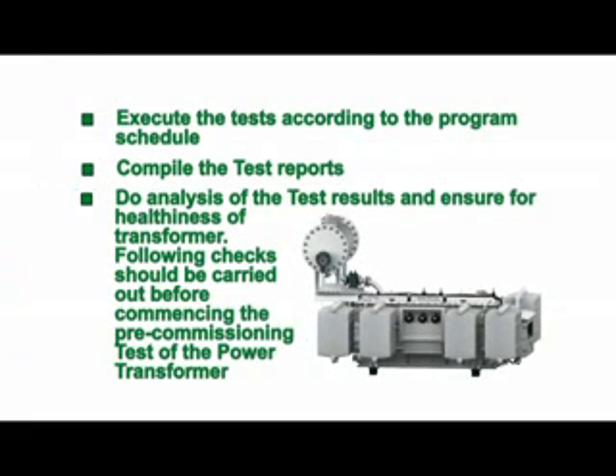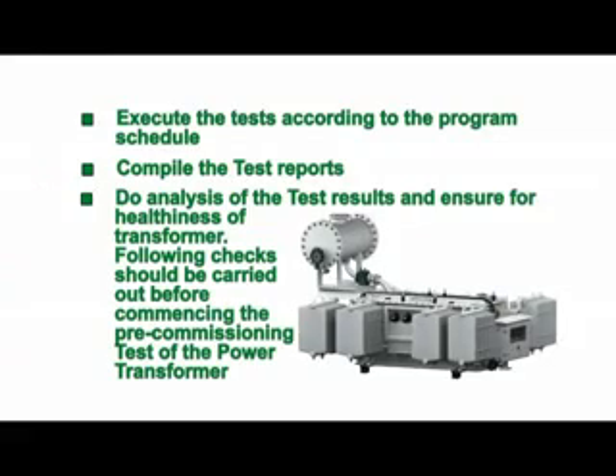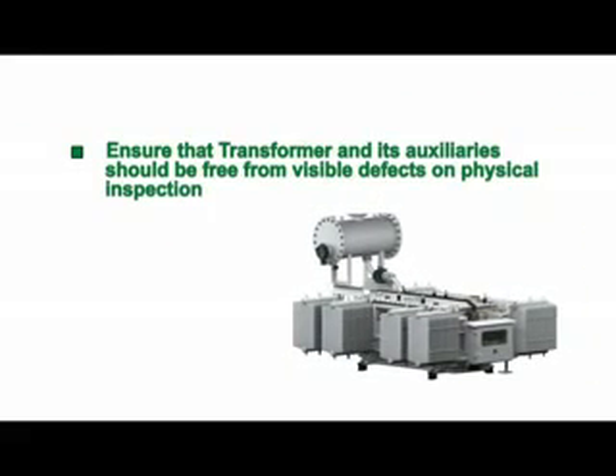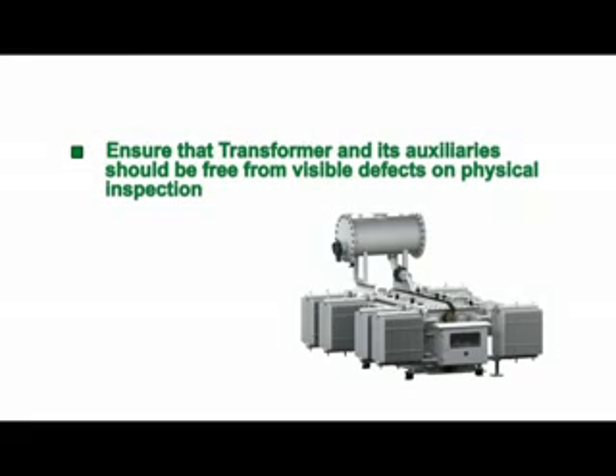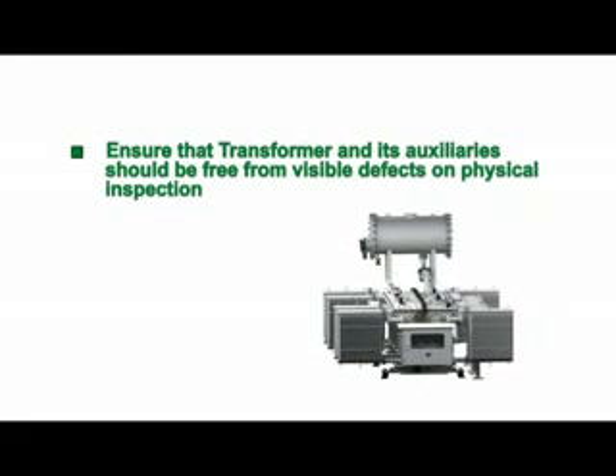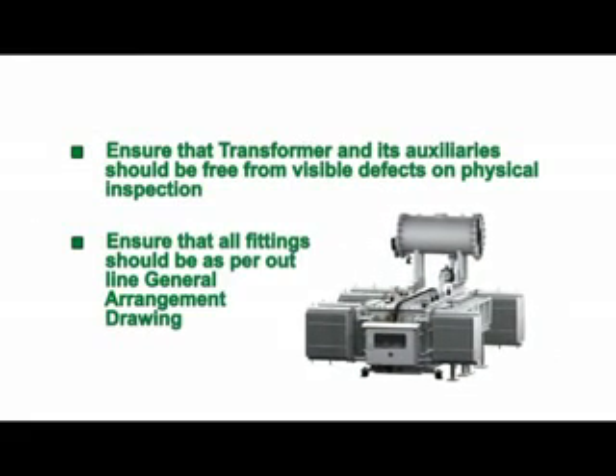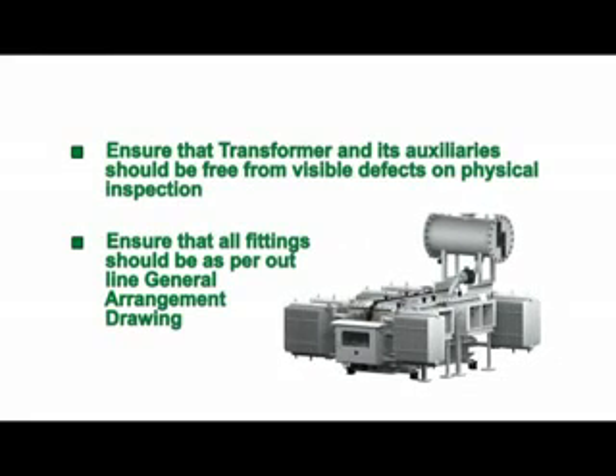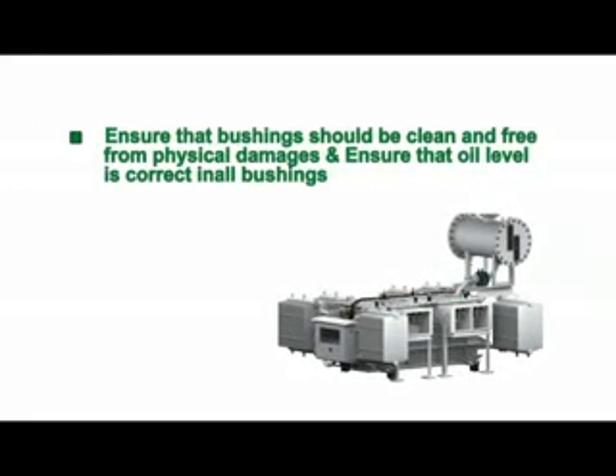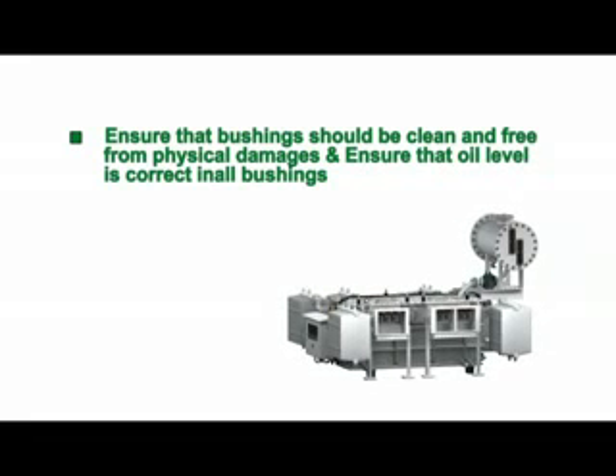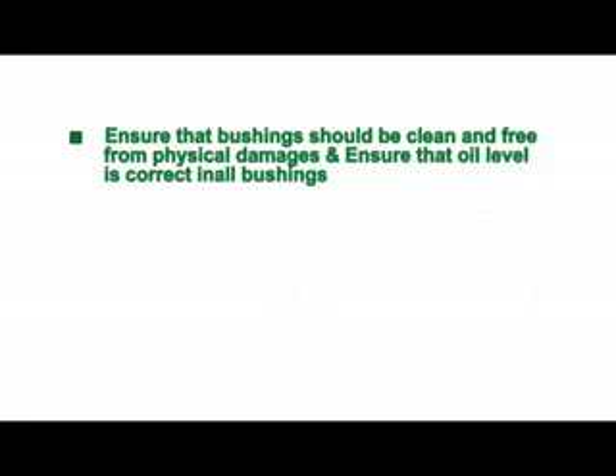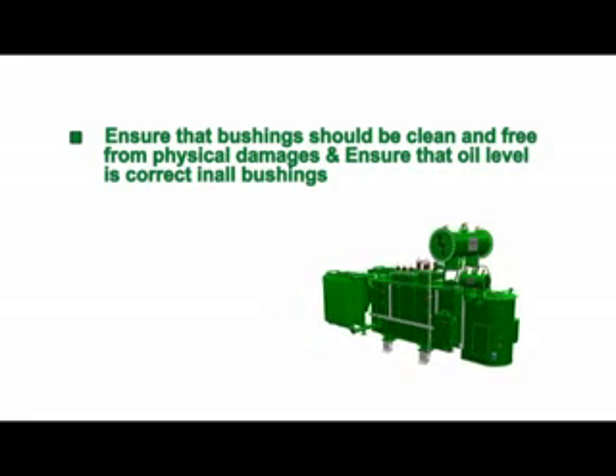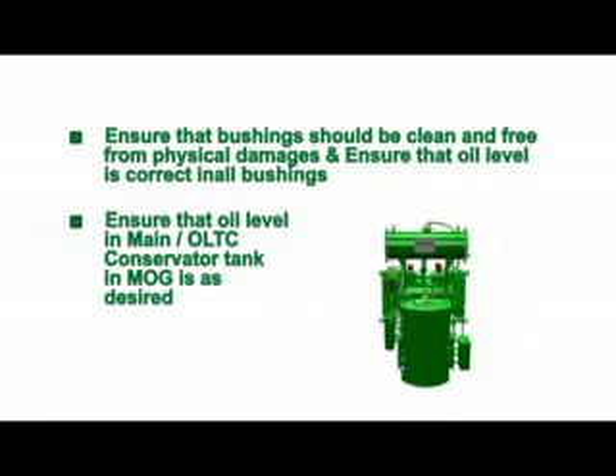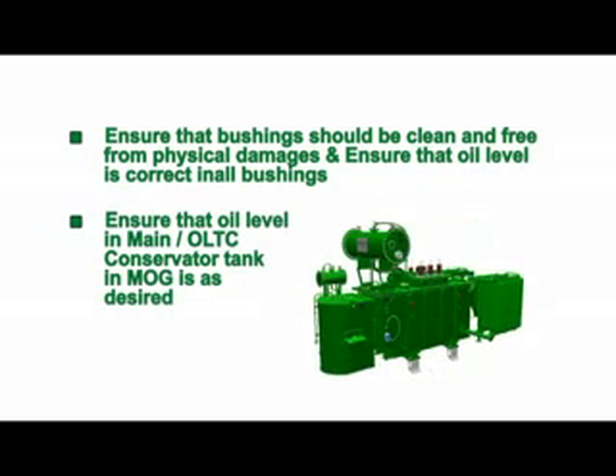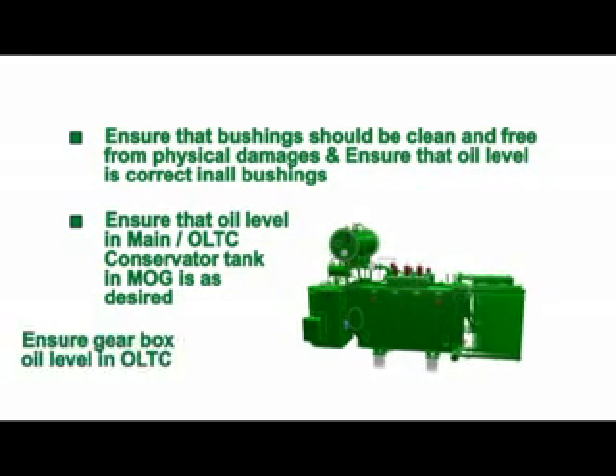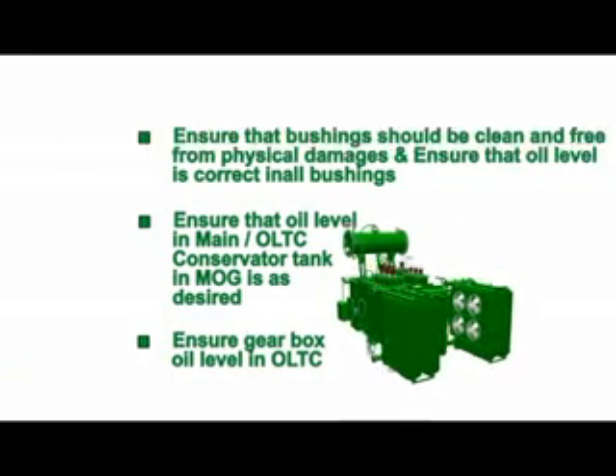The following checks should be carried out before commencing the pre-commissioning test of the power transformer. Ensure that the transformer and its auxiliaries are free from visible defects on physical inspection. Ensure that all fittings are as per the outline general arrangement drawing. Ensure that bushings are clean and free from physical damage and that the oil level is correct in all bushings. Ensure that the oil level in the main OLTC conservator tank, in MOG, is as desired. Ensure gearbox oil level in OLTC.